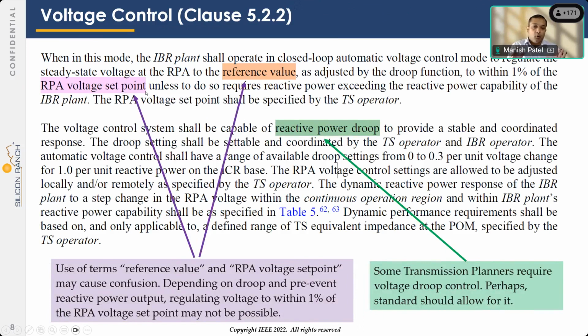I'll stop right there. All I want to say, and you have to go back and think about this, maybe look up some control block diagrams, try to put 2 and 2 together. I think the use of terminology, reference value, and voltage set point may have caused some confusion. So we need to make sure that in the next revision, this is all clarified. Also, depending on droop and pre-event reactive power output, regulating voltage to within 1% of RPA voltage set point may not be possible. I think the intent here may be to regulate the voltage to within 1% of the reference value adjusted by droop function.